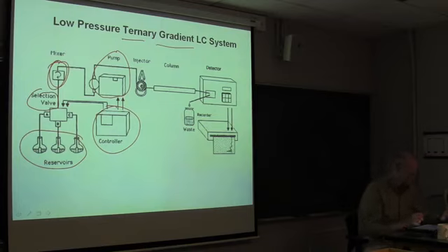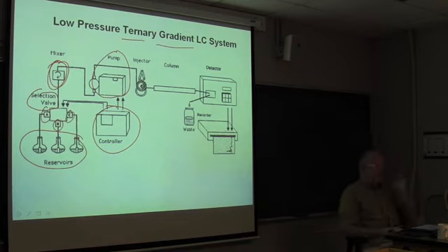This is a cheaper way to go because you only have one high pressure pump. But it's a lot harder to get the mixers to work, for one thing. It's very tricky to make these valves really, really toe the mark and be open and closed for exactly specified periods of time. And they have to be opening and closing very rapidly so that you don't have big slugs to mix, but little tiny slugs to mix, because it's much easier to mix small volumes than it is big volumes.